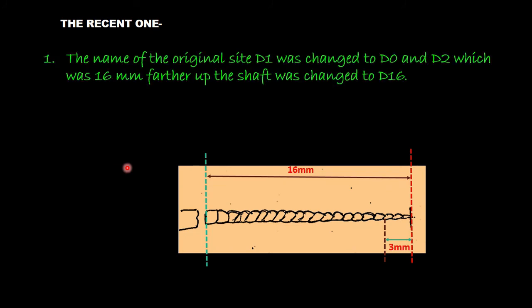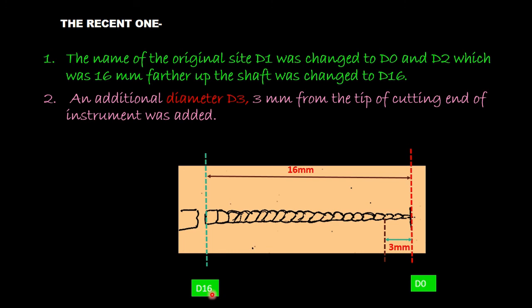The changes that have been proposed: the tip diameter that previously we used to call D1 was changed to D0. And 16 mm from this D0, we used to have D2 but now we call it D16. And 3 mm from D0, we have D3. So an additional diameter D3, 3 mm from the tip of the cutting end of the instrument, was added.